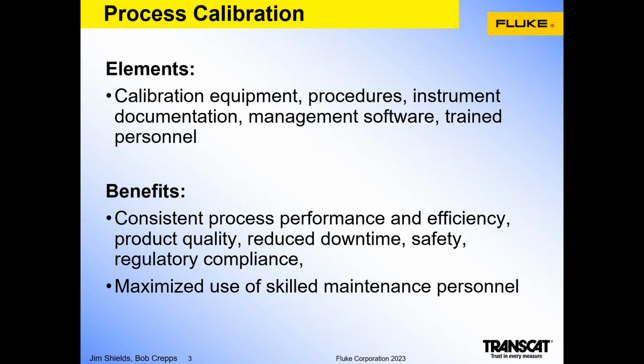So elements of a process calibration system include the calibration equipment, as in the calibrator, accessories such as pumps and things of that nature. The instrument documentation is required. It requires management software to manage the data that these documenting calibrators capture. And your personnel need to be trained on how to utilize and operate these elements of this calibration process.